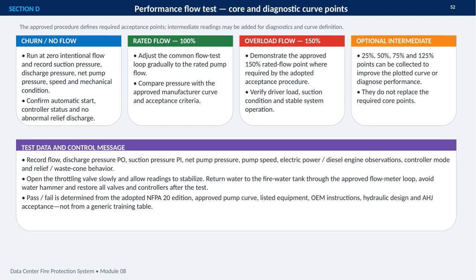Throughout the test, I record all relevant pressures, flow, speed, power or engine observations, controller mode, and relief behavior. I open the throttling valve slowly, stabilize readings, avoid water hammer, return water through the approved loop, and restore the system afterward. Pass or fail must follow the adopted requirements and approved equipment documentation, not a generic table.